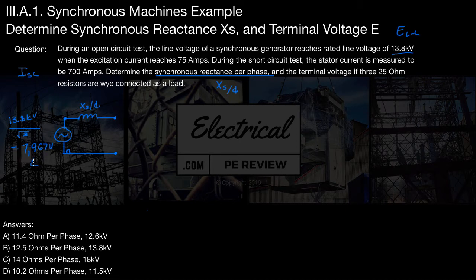We're going to call that E0. Next, to find our synchronous reactance, we know that synchronous reactance can be found by dividing our line-to-neutral voltage E0 by our short circuit current from our short circuit test. So we found E0 to be 7,967 volts.